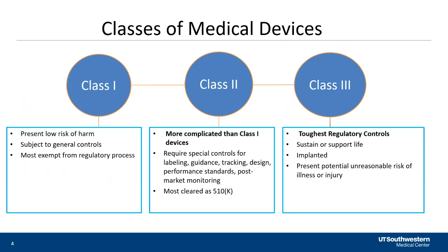Class 3 devices involve the toughest and most stringent regulatory controls because they support or sustain life, they are implanted, and present potential for unreasonable risk of illness and injury.